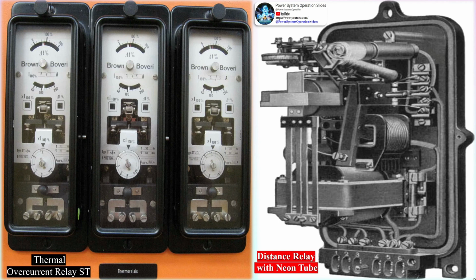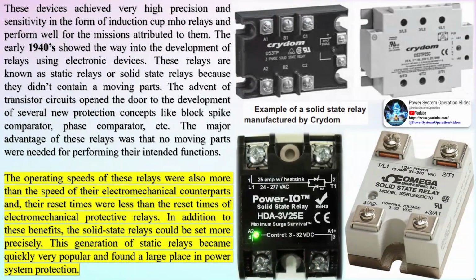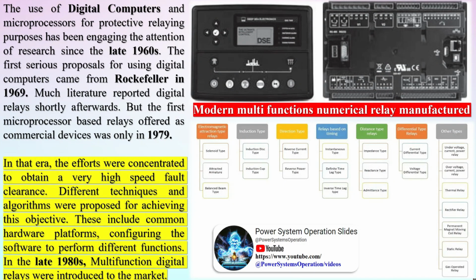The early 1940s showed the way into the development of relays using electronic devices. These relays are known as static relays or solid-state relays because they didn't contain moving parts. The advent of transistor circuits opened the door to the development of several new protection concepts like block spike comparator, phase comparator, etc. The major advantage of these relays was that no moving parts were needed for performing their intended functions. The operating speeds of these relays were also more than the speed of their electromechanical counterparts and their reset times were less than the reset times of electromechanical protective relays.